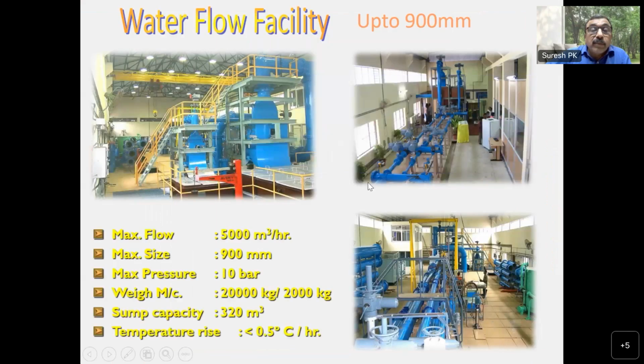So you can see that this is the diverter system. The maximum flow through the facility is 5,000 meter cube per hour. So the flow meter is assembled here. Unfortunately, I don't have the figure of a constant head tank. A constant head tank is outside. This is the system in which you assemble the flow meters. This is the system by which you determine the flow rate or flow volume measurement.